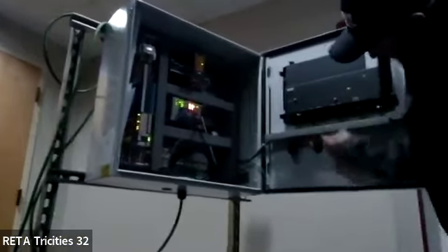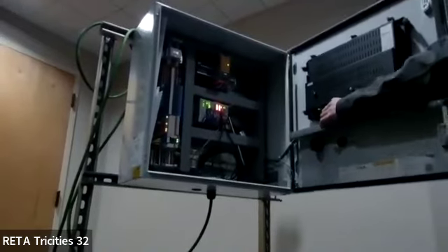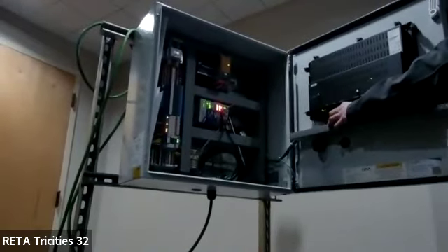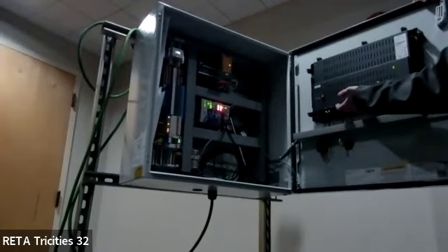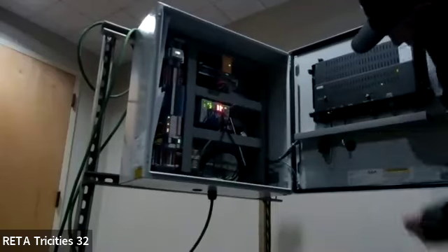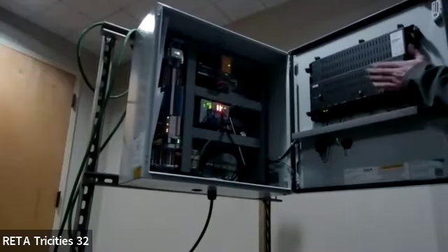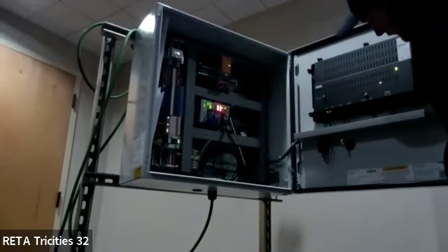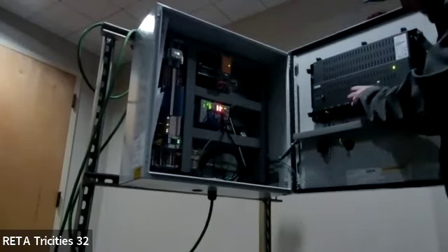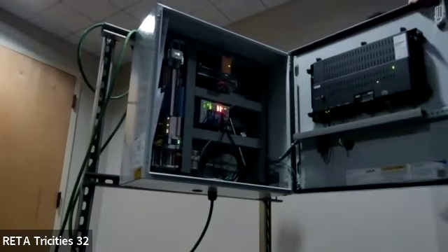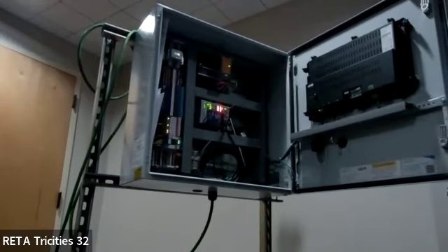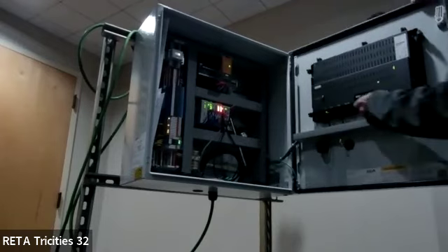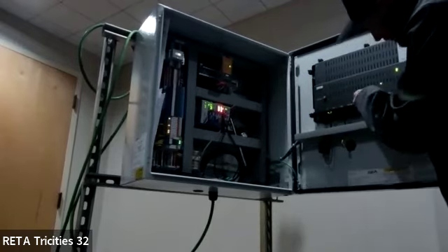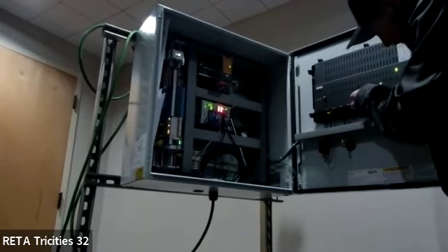You've got the IO, you've got the USB from the outside of the panel. You do not have to open the panel, just put your USB in. You also have another one where you can plug a drive into here in case you have an issue with this. And then this is the power to the processor. Literally takes you like 15 minutes. This is where the flash card is going to be, in there. So if you have an encrypted flash card, you can get into one of those also. Those have been known to rattle loose and you can lose the screen.